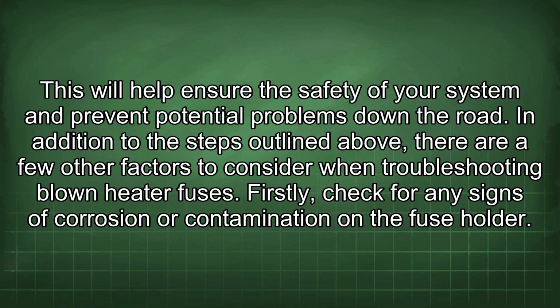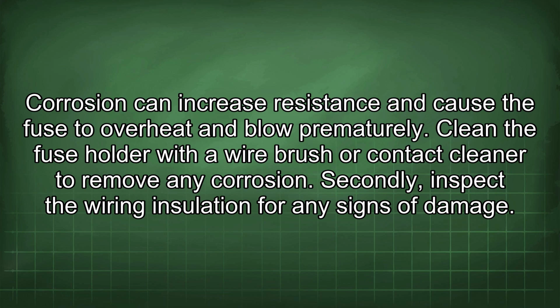In addition to the steps outlined above, there are a few other factors to consider when troubleshooting blown heater fuses. Firstly, check for any signs of corrosion or contamination on the fuse holder. Corrosion can increase resistance and cause the fuse to overheat and blow prematurely. Clean the fuse holder with a wire brush or contact cleaner to remove any corrosion.